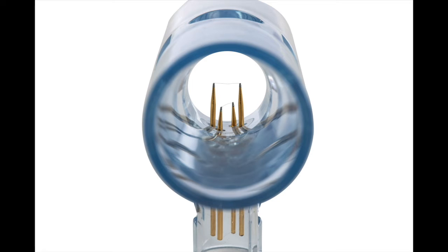Now, the exhalation flow sensor is the most likely cause of the alarm. And what I want to do is look at my exhalation flow sensor. So I'm looking right through. And what you notice is it may be hard to see. You might need a larger screen to see this.